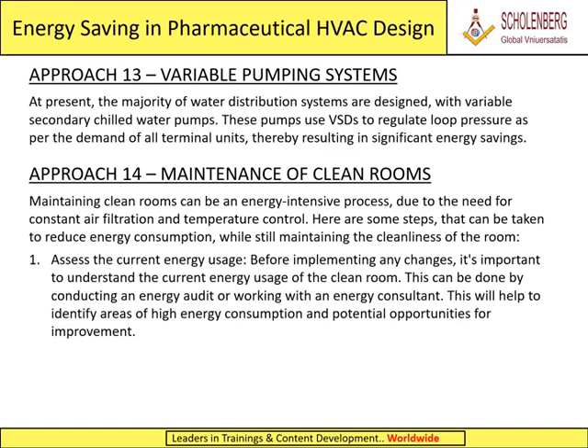Approach 13, Variable Pumping Systems. At present, the majority of water distribution systems are designed with variable secondary chilled water pumps. These pumps use VSDs to regulate loop pressure as per the demand of all terminal units, thereby resulting in significant energy savings.